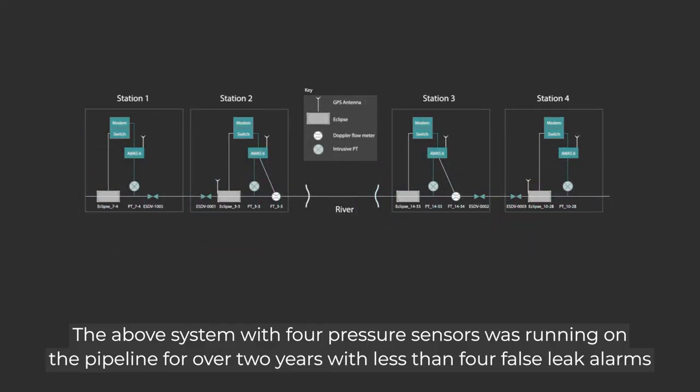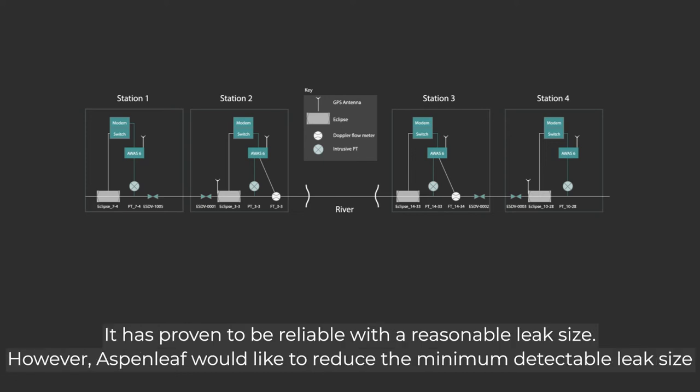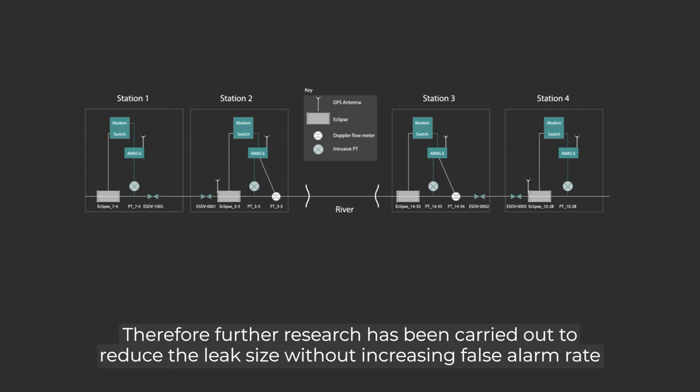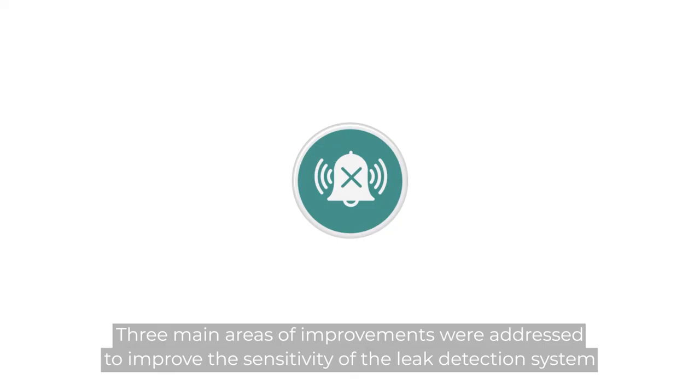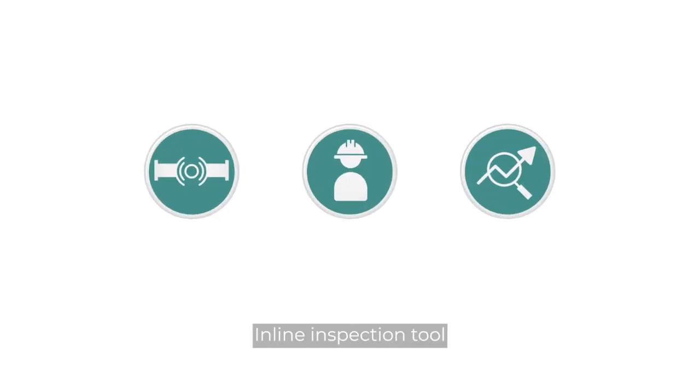The above system with four pressure sensors was running on the pipeline for over two years with less than four false leak alarms. It has proven to be reliable with a reasonable leak size. However, Aspen Leaf would like to reduce the minimum detectable leak size. Therefore, further research has been carried out to reduce the leak size without increasing false alarm rate. Three main areas of improvements were addressed: field instrumentation, pipeline operations, and in-line inspection tool.